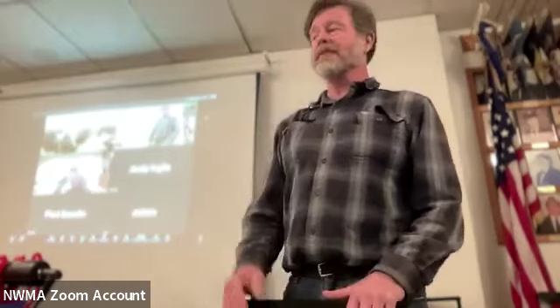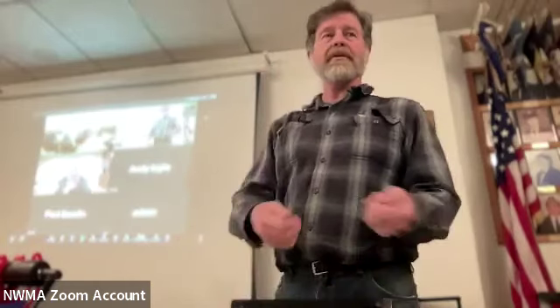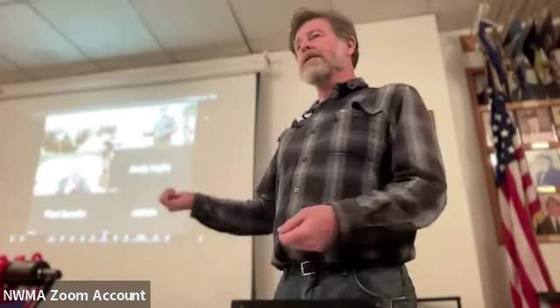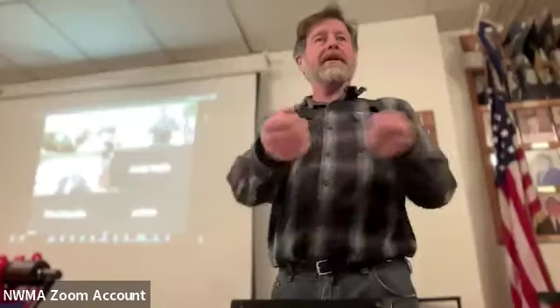If it's AC, floating neutral, and we'll dig into that a lot, but that happens on stuff. I've run into boats, you put the meter on the panel and there's 70 volts. How weird is that? There's 110 coming into the boat, and then here it's 70, because that neutral is loose.